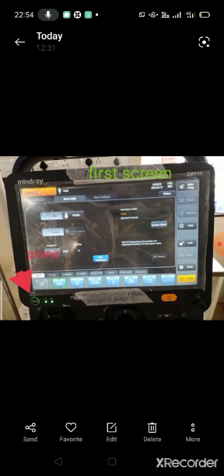And you will have a system check option here. In this system check option, never bypass the system check when you are connecting the ventilator for the first time. What you have to do for the system check is connect the tubings and short the tubings. You have to connect the Y-piece towards the right side. There is one connector where you can connect the Y-piece end of the tubings. You have the flow sensor test, O2 sensor test, everything there. Never bypass the O2 sensor calibration. There is a skip option there, so don't use that.